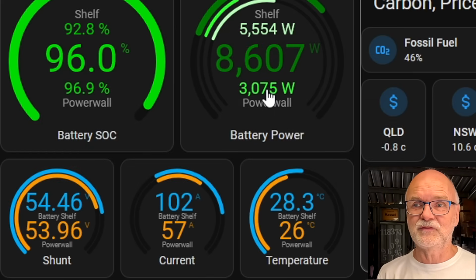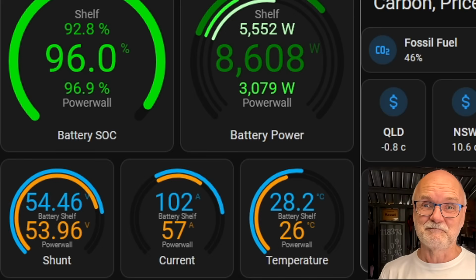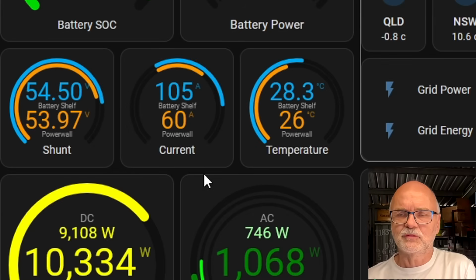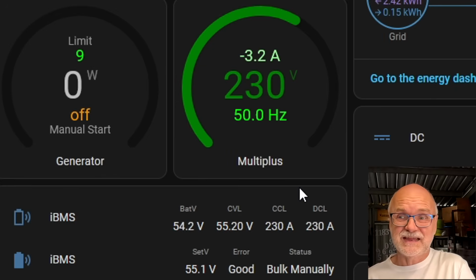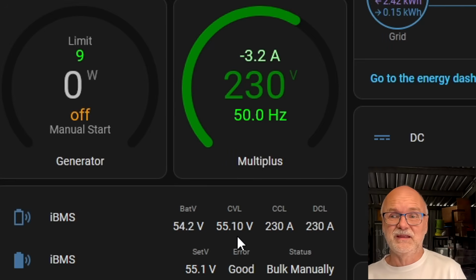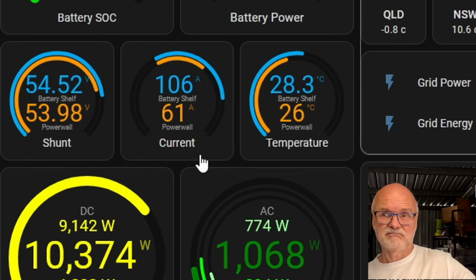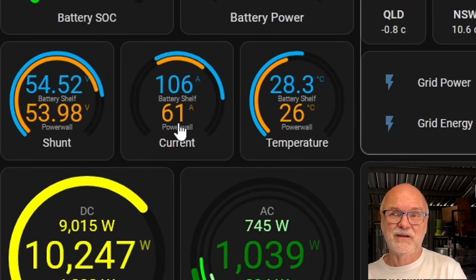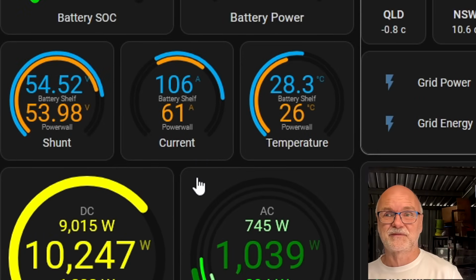Let's give it a few minutes and we should hit 60 amps, our maximum charge current through this breaker. All right, we've now reached 60 amps, and it only took 2 minutes. It can take up to 20 seconds now until the CVL actually lowers to 55.1. There it is, 55.1. Now it checks again in 20 seconds if the current is still over 60 amps.